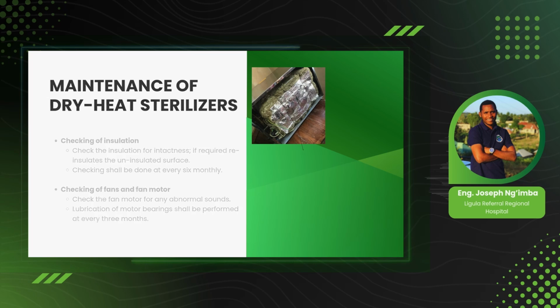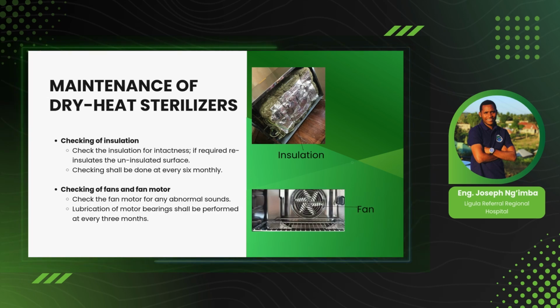Another thing that we do during maintenance is to check the insulation. This is the most important part to check, because when the insulation is poor, it can cause burns to the user or anybody else who passes and touches the machine. So you need to check the intactness of the insulators. They are this kind of material, as you can see in the picture, a sponge-like material wrapped around the chamber on the outside, so that it prevents conduction of heat from the chamber to the surface of the machine. If there is a part missing insulation, you insulate it so that there is no case of burns to the users. This kind of maintenance is checked on a 6 months basis.